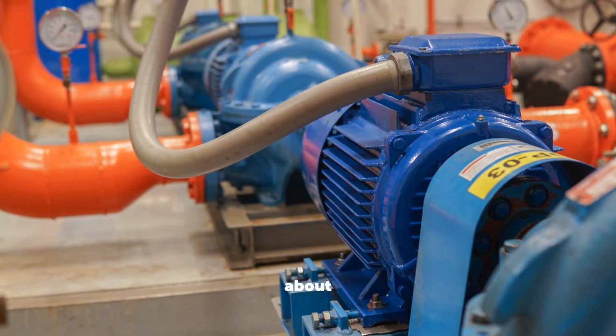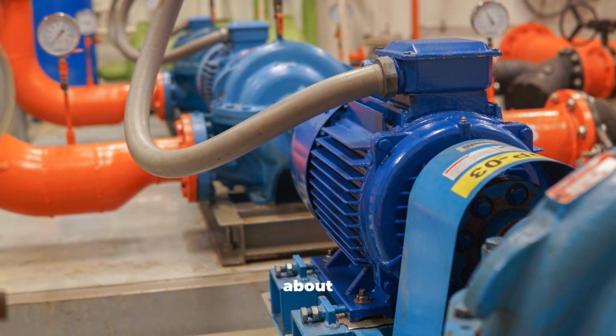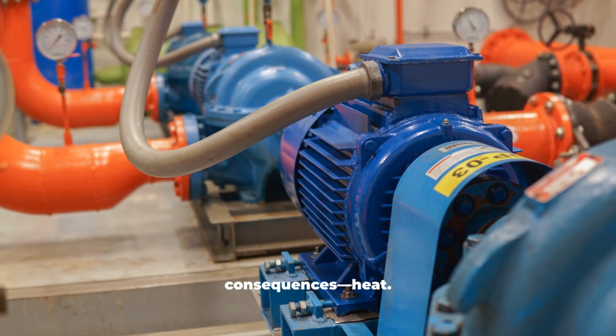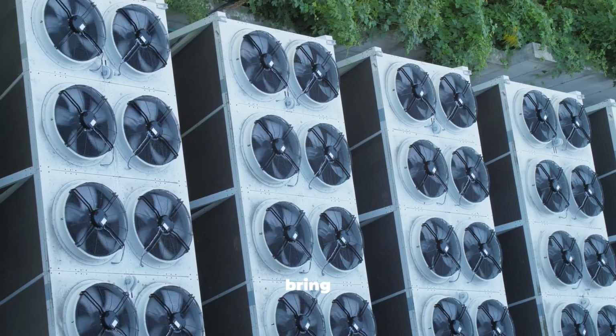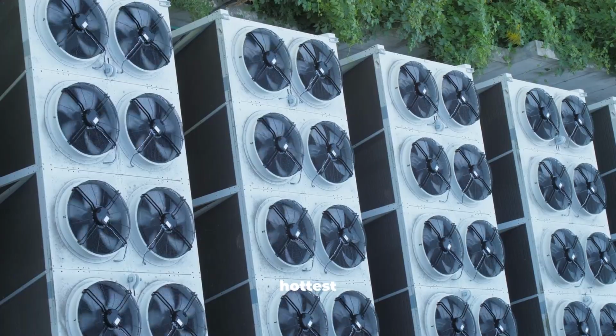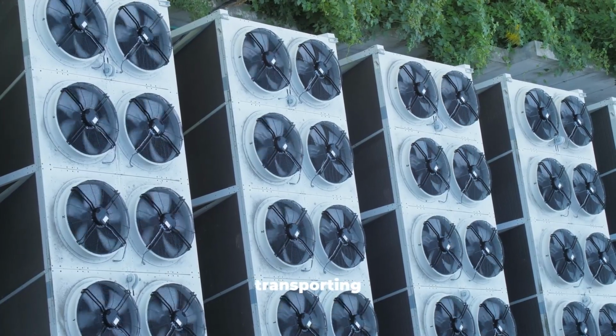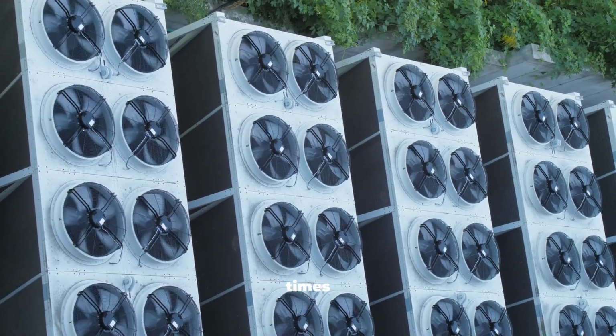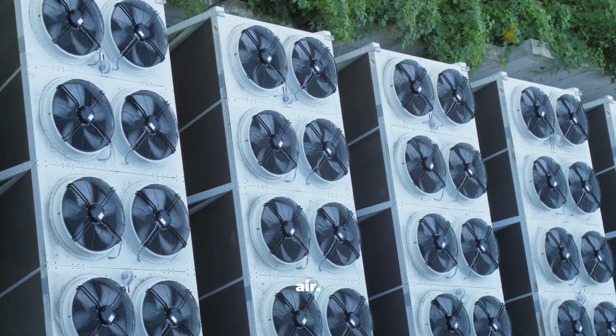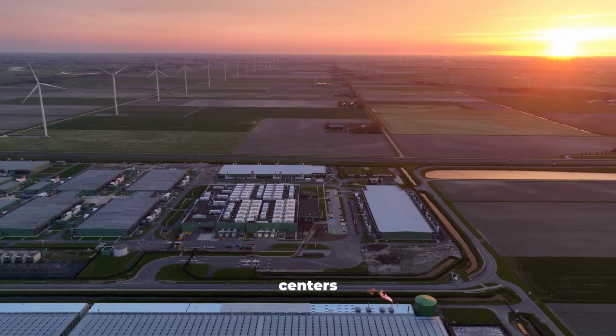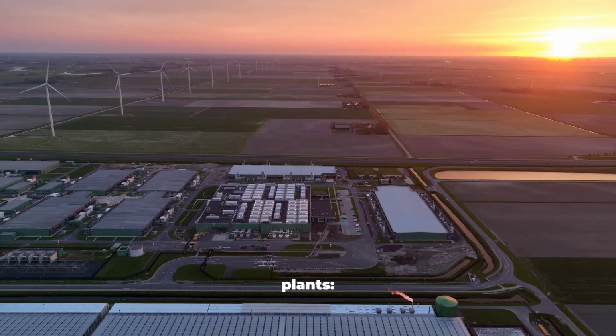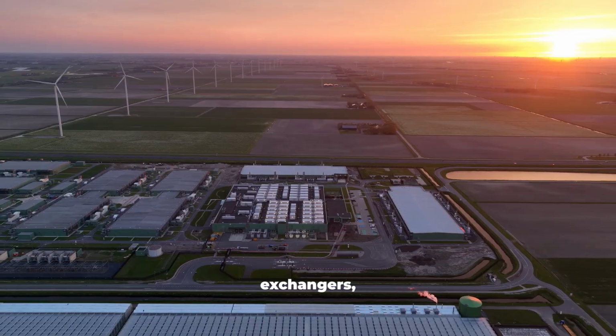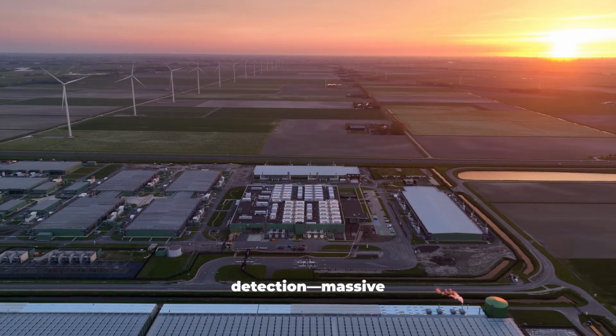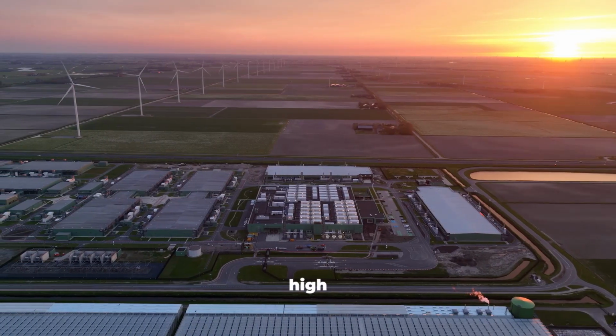It wasn't just about delivering power. It was about managing the consequences: heat. Liquids bring cooling directly to the hottest components, absorbing and transporting heat thousands of times more effectively than air. Liquid-cooled data centers look more like processing plants: pumps, exchangers, cooling towers, leak detection, massive construction, high stakes.